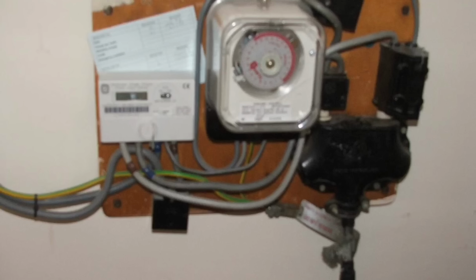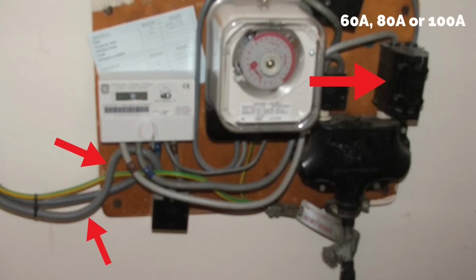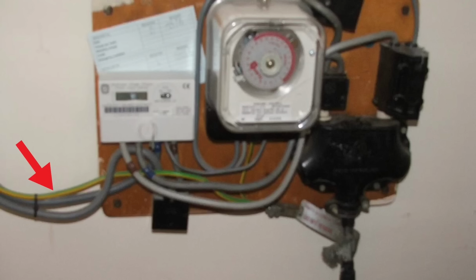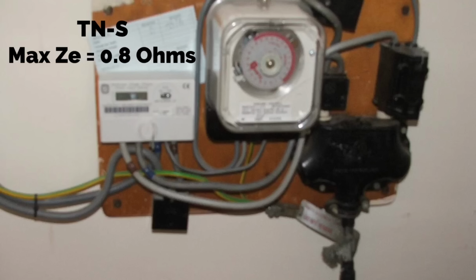arrangement TNS. The cutout fuse in this installation is 60 amps, but could have been 80 amps or 100 amps. The double insulated meter tails are 25 millimeters squared, and the earthing conductor from the MET into the distribution board is size 16 millimeters squared. All this information needs to be inputted into our test paperwork, along with either the measured reading for external earth fault loop impedance or the maximum external earth fault loop impedance, which for a TNS earthing arrangement is 0.8 ohms.